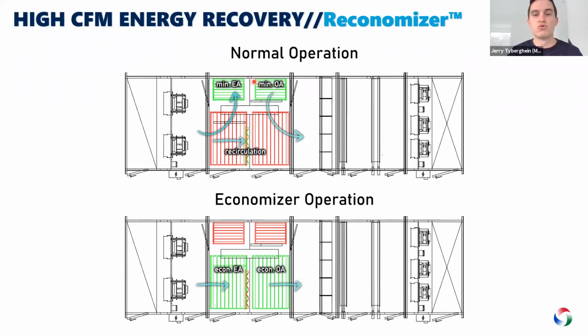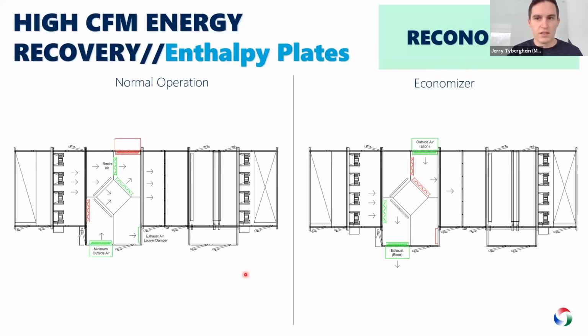On the bottom, that's normal operation, by the way. On the bottom is economizer mode. You just shut these two dampers, so now you're not going through the wheel at all. And then you exhaust out here, and you bring in outside air here, and you're not recirculating anymore. And then last slide, this is the economizer concept with enthalpy plates or sensible plates.